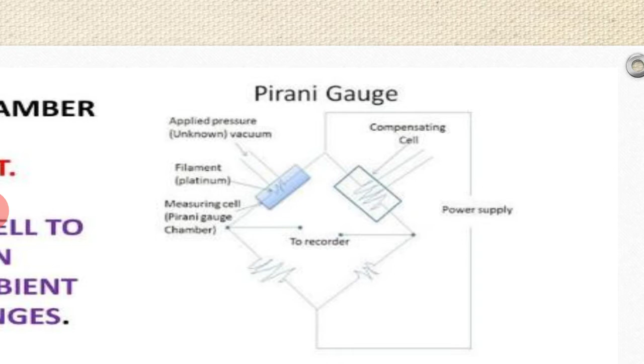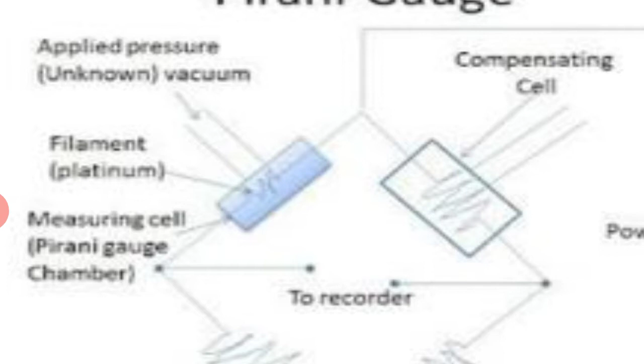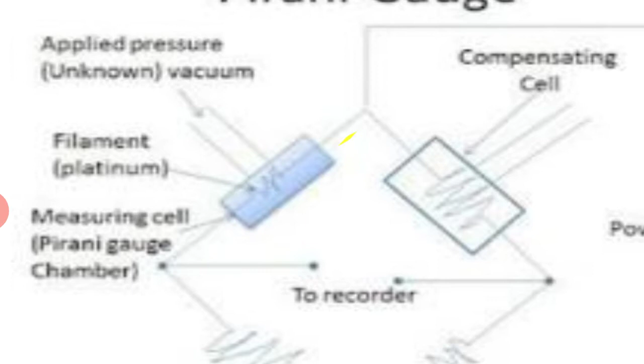Here you can see in the diagram the compensating cell, which is introduced for compensating purposes. If any variation is there due to the ambient temperature, it will be compensated with the help of this. The applied pressure or unknown vacuum will be given to this filament. The filament, platinum, is inside here. Vacuum will enter here, and this is the compensating cell.